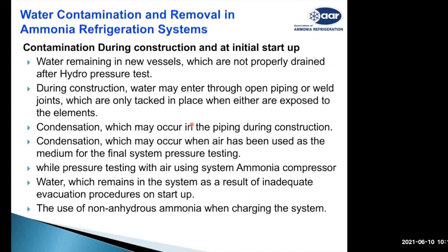In the late night, dew will get formed on these open pipes lying in the system, or the pipes which are not properly capped. And then the next day morning, when people start welding or using these pipes, they will not take care of removing the dew formed on the pipe, and this dew will get converted into water and it will remain in the plant. This condensation or dew formation is what I've been told.